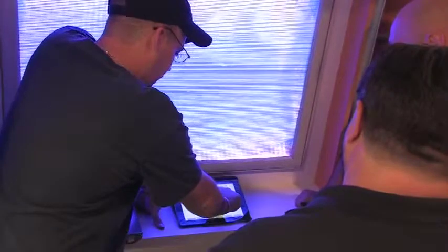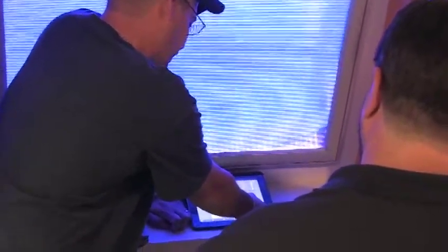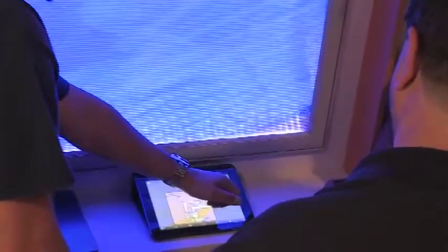So on these you obviously see your min and max. Whatever your flow set point would be that you would see here, you would subtract this, and then that should be your flow for your exhaust. That's what you would want your set point to be for the exhaust. So right now, my actual flow is just about 400 with the set point of 400. So you see my exhaust set point is 0 because I'm subtracting 400 from that, which is giving me the set point for this.